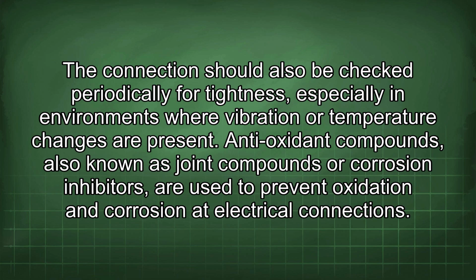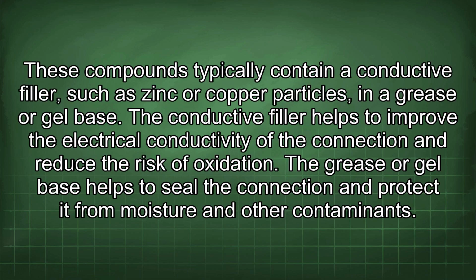Antioxidant compounds, also known as joint compounds or corrosion inhibitors, are used to prevent oxidation and corrosion at electrical connections. These compounds typically contain a conductive filler such as zinc or copper particles in a grease or gel base. The conductive filler helps to improve the electrical conductivity of the connection and reduce the risk of oxidation. The grease or gel base helps to seal the connection and protect it from moisture and other contaminants.